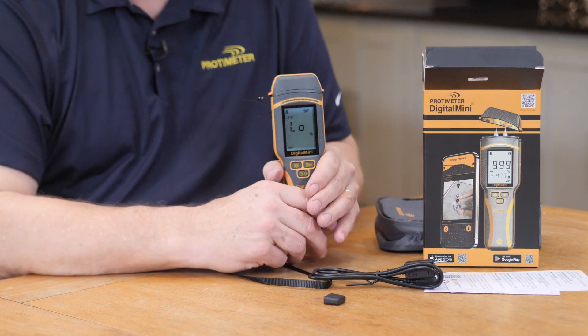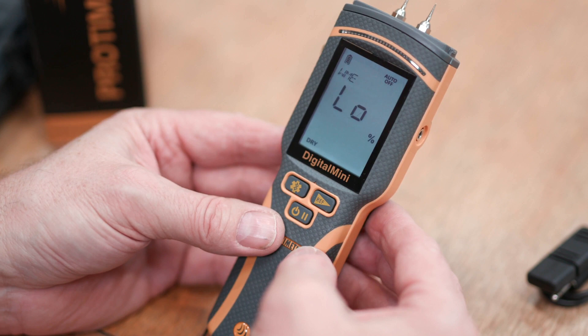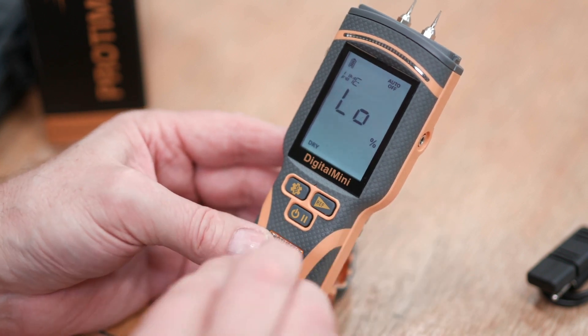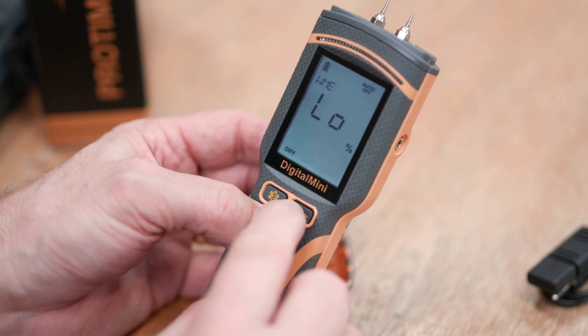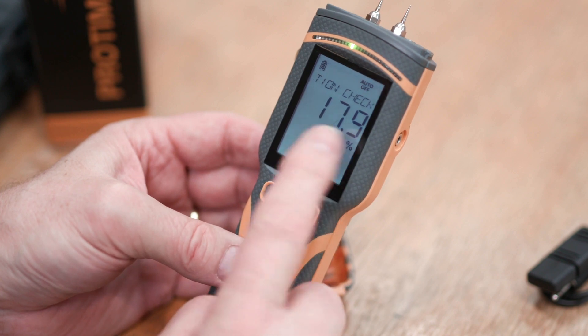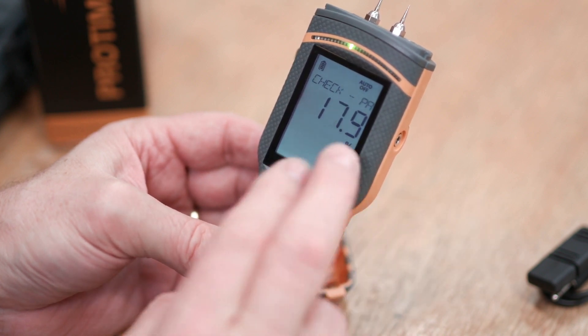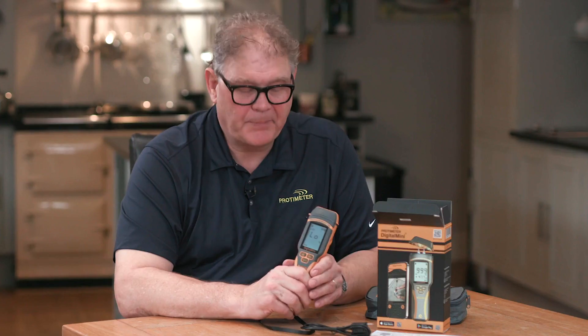The meter can also check its own calibration automatically every 50 power cycles. You can also initiate it manually by holding the lower button and pressing and holding the second button. The meter will enter calibration check mode — as you can see, it says pass here with the reading displayed. So that's the Protimeter Digital Mini, a pin-type moisture meter for use in building materials. Thanks for watching.